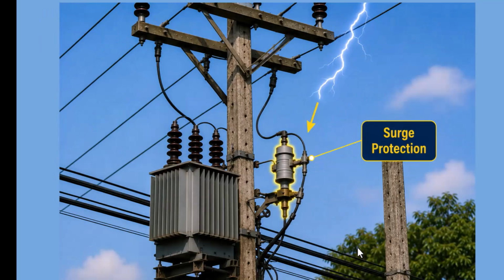What about lightning? Remember, these conductors and pieces of equipment are outdoors. They may be exposed to lightning and other transient overvoltages. A very short voltage surge can produce an extremely high voltage that may damage insulation or connected equipment. That is why surge protection devices are used. So even if lightning itself is not visible in this photograph, the system should make you think about surge protection.